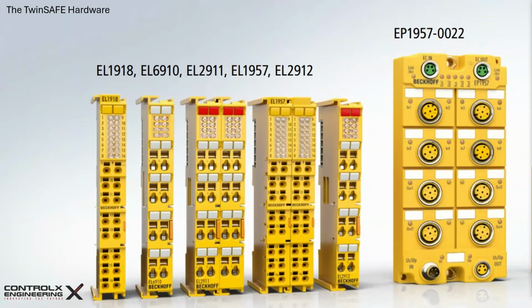true or false, the safety input terminals like the EL1904 aren't just looking for 24 volts, they're looking for clock signals. The terminal sends out unique pulses, clock 1 and clock 2, to the connected device like an e-stop. This allows the safety input terminal to detect short circuit conditions. It is a level of diagnostic intelligence that goes far beyond a simple high-low signal. Every yellow terminal also performs internal self-tests every time it powers up and while it's running.